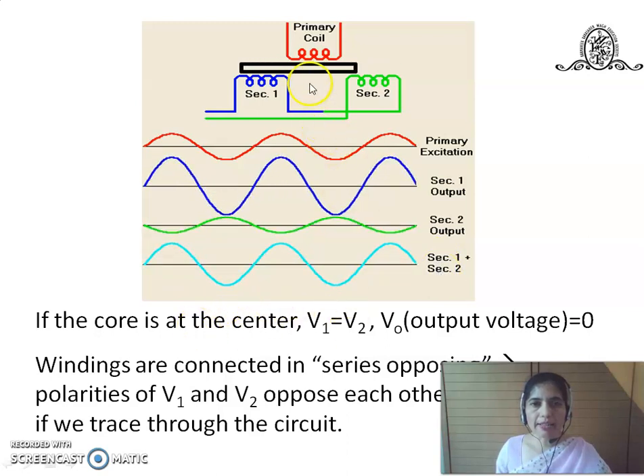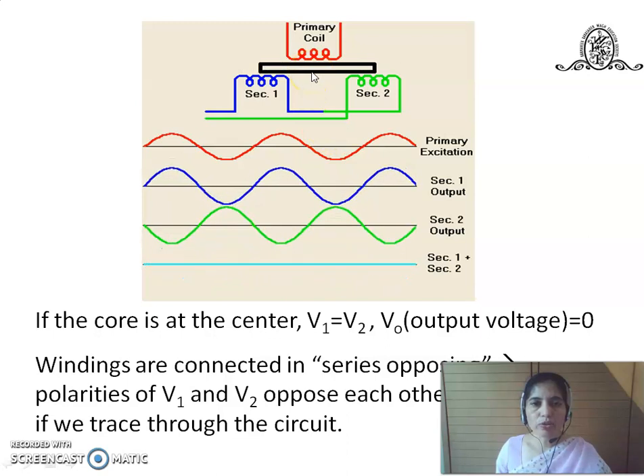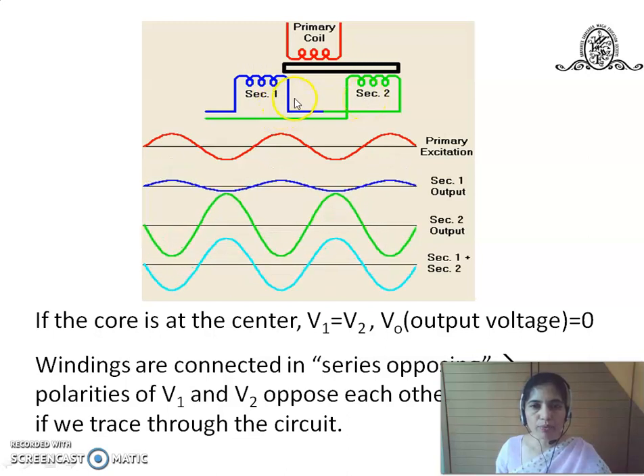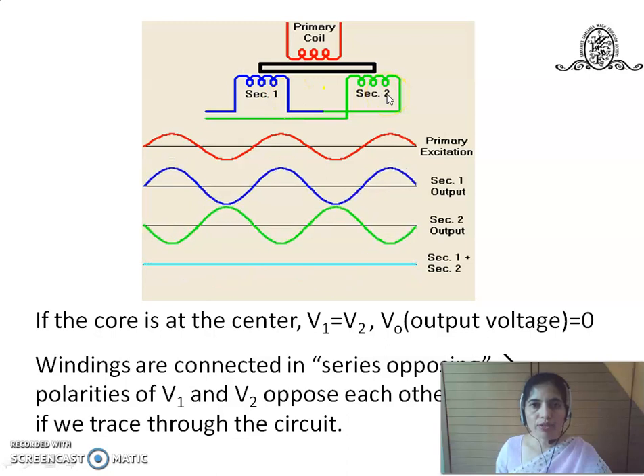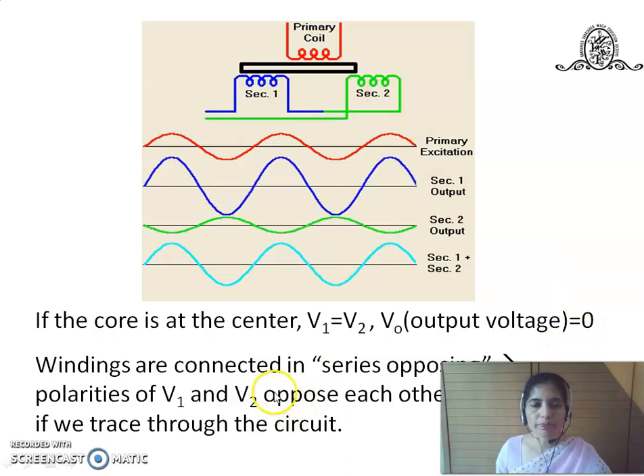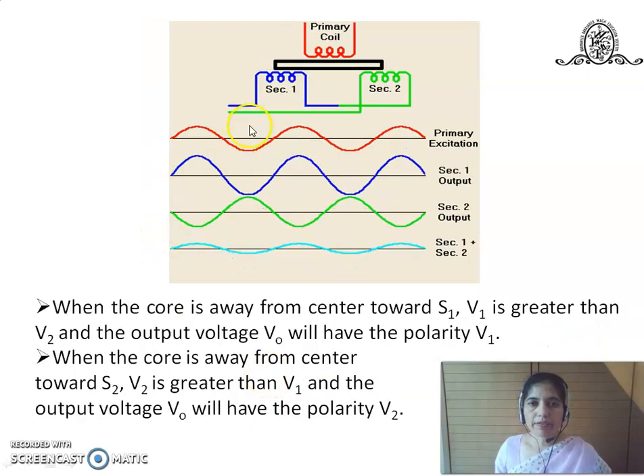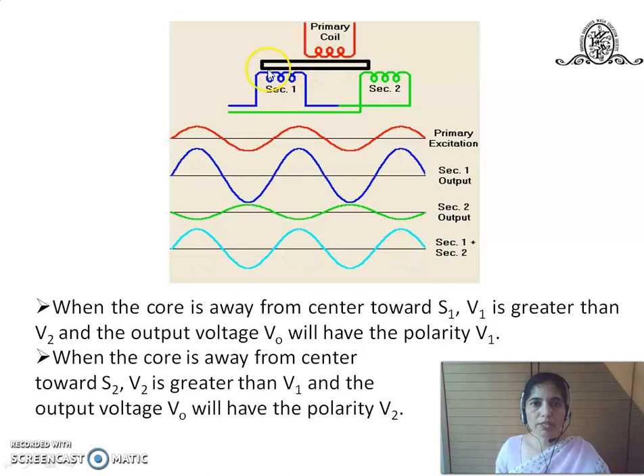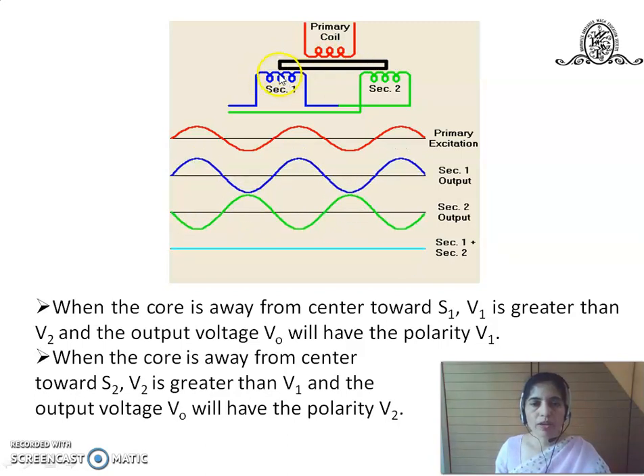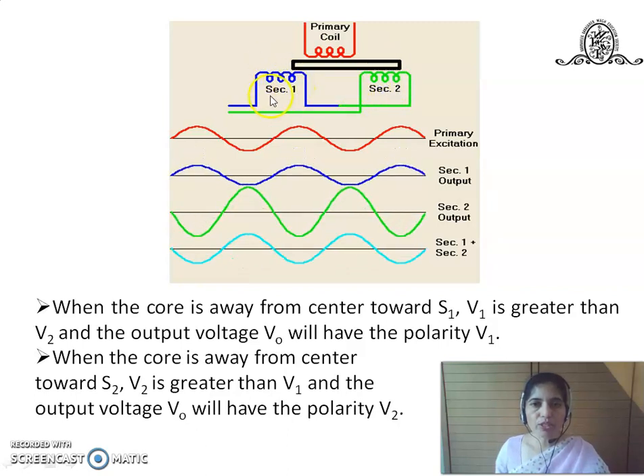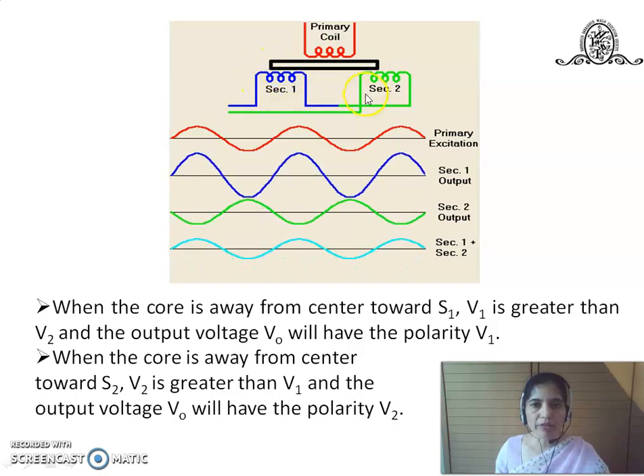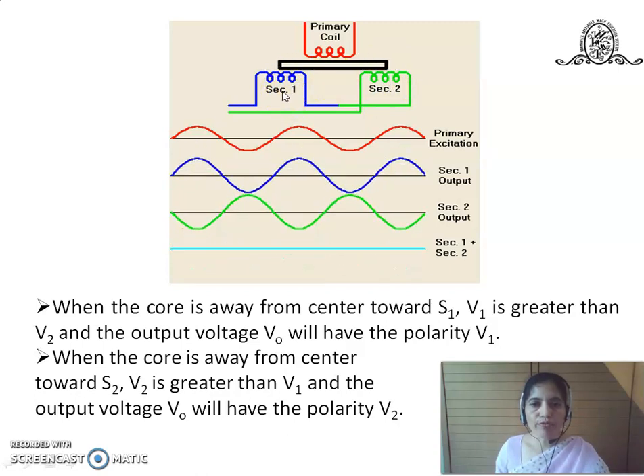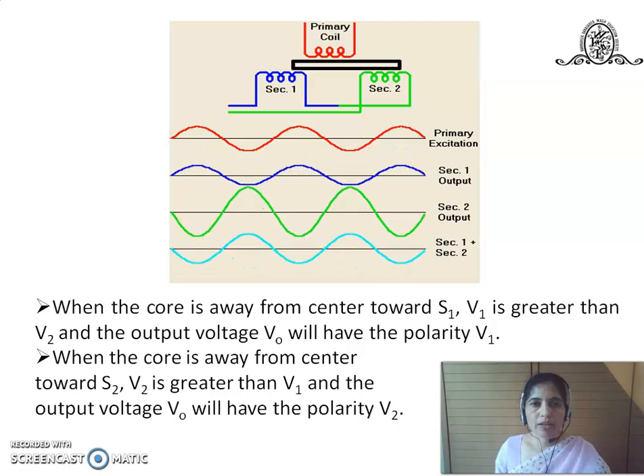So if the core is exactly at the center, then it will induce the same voltage in both the secondaries. But since both the secondaries are connected in series opposition, these two voltages will cancel each other out, and the output voltage will be 0. Now, if the core moves towards secondary 1, that is S1, it will induce more voltage in S1 than in S2. So V1, the voltage induced in S1, will be greater than V2, and the output voltage V0 will have the polarity of voltage V1.